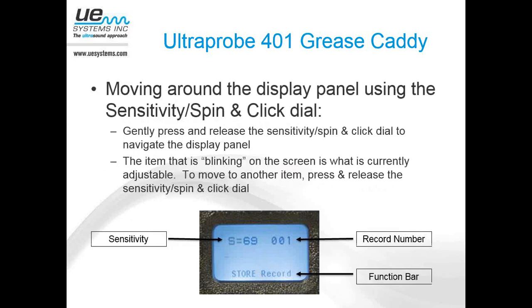So now, moving around the display using the sensitivity spin and click dial. Here's a little closer shot of that main display. We're looking at 3 different things currently on this particular screenshot. We can see here we have the S equals, and we see a number there. That's the sensitivity where we have it set. 0 is the lowest, and 70 is the highest. Keep in mind, though, that the sensitivity is going to have no effect on the decibel level. The sensitivity, you can compare it to a volume, but really we're just trying to dial it in to be able to measure how much noise is being generated from that bearing.